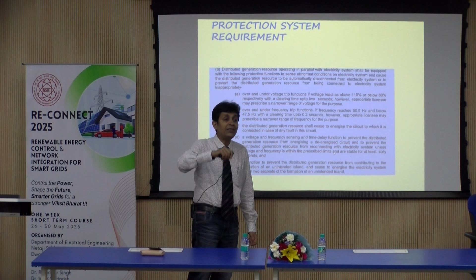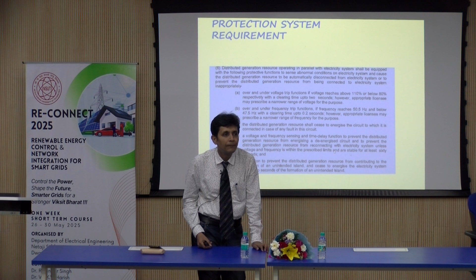Then what further does it guide? It guides you about the protection you need. It says you must have over and under voltage protection. It must have under frequency and over frequency protection. It must have a function that is the most important function, anti-islanding protection. Can any one of you explain what anti-islanding protection of inverters for solar PV is? If it is not there, what is going to happen? Anyone sitting here can explain that feature required? Let me explain.